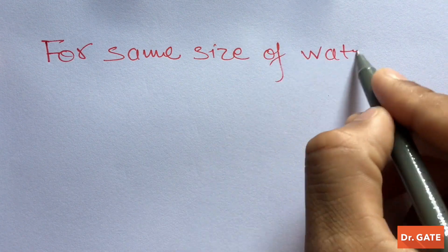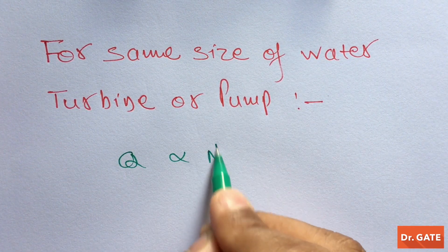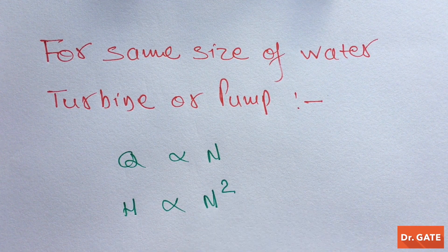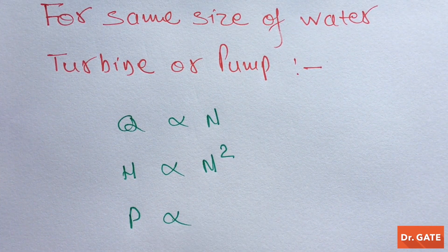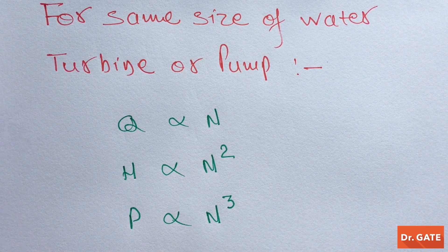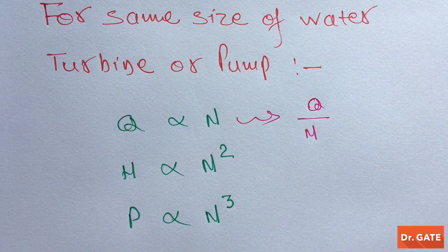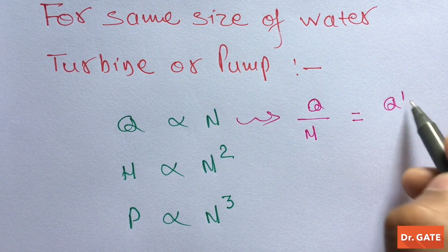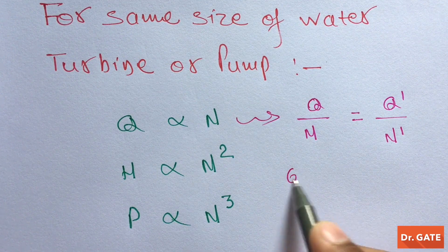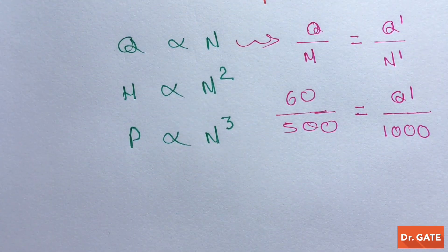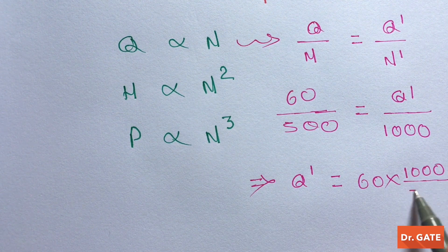From our previous class we know that for the same size of water turbine or pump, discharge is proportional to N, head is proportional to N squared, and power is proportional to N cubed. So from here, initial discharge upon initial speed equals final discharge upon final speed. Putting in the given values, the final discharge is 120 liters per minute.